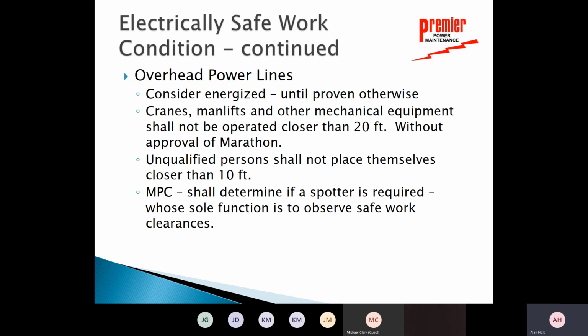Then they have a complete section on overhead power lines. So consider overhead power lines energized until proven otherwise. Okay, that's pretty standard verbiage, but I want us to understand that we should always consider overhead power lines energized unless it's proven dead. And proven dead does not mean that a Marathon team member or Marathon engineer or anybody from Marathon comes up and says, yeah, it's dead. That's not proven dead. Proven dead means verification by electrical test.